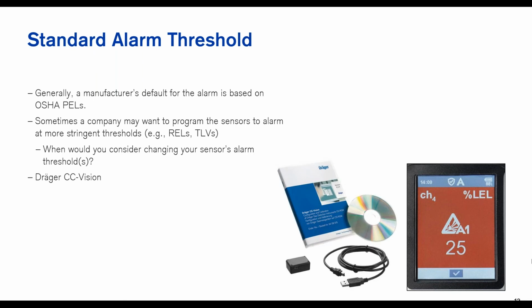And then you'll get to a certain point on the flammability range where it more or less goes into a protection mode. And it essentially shuts off that sensor and says, I'm not shutting up until you go outside, you shut me down, and you reboot me from scratch. And so understanding that if my sensor won't silence, then hey, I'm in a high alarm or a latching alarm, and I need to understand what the severity of that actually is.